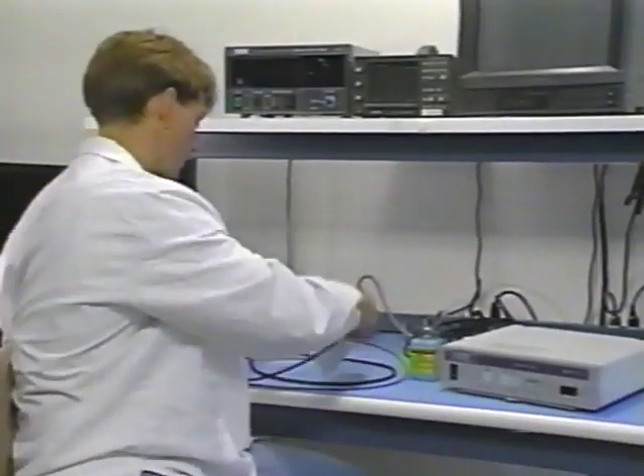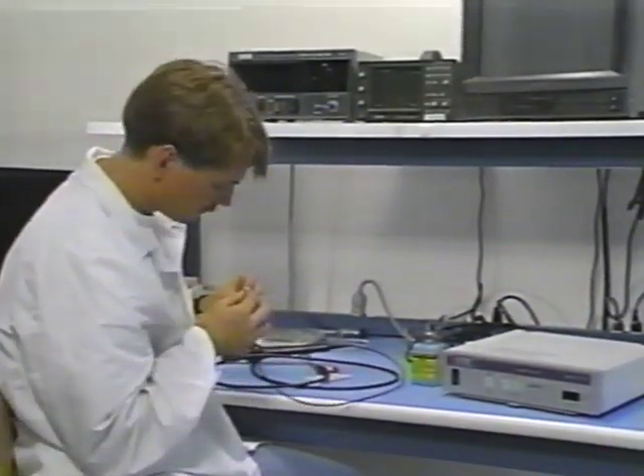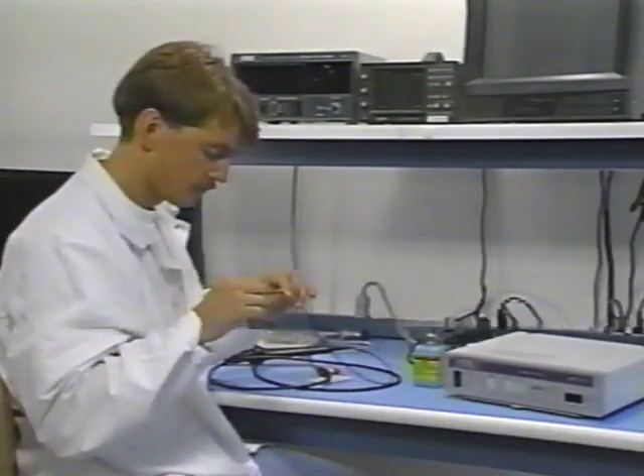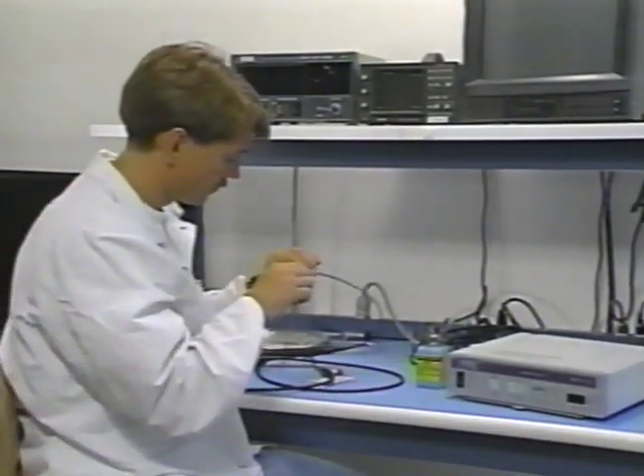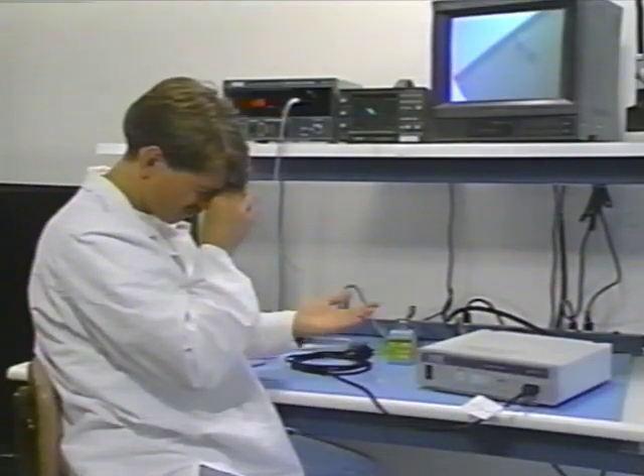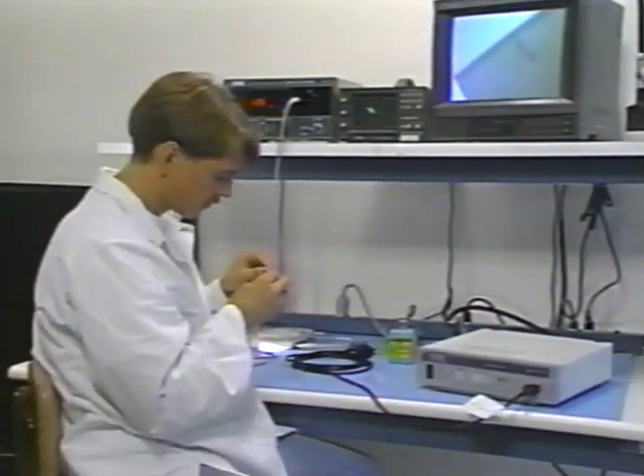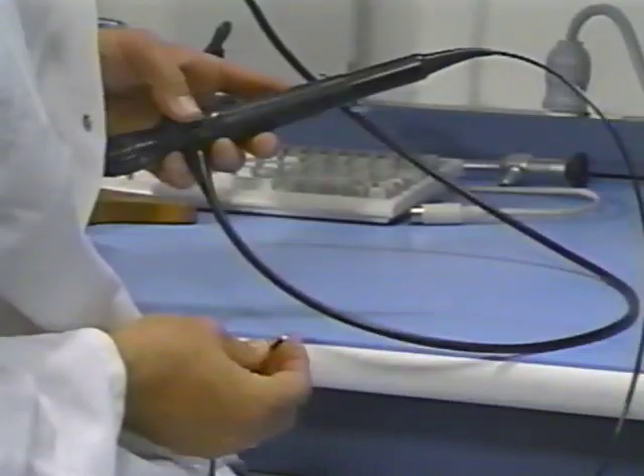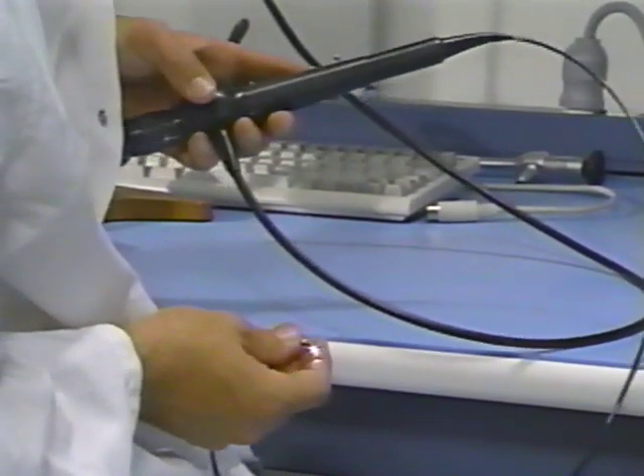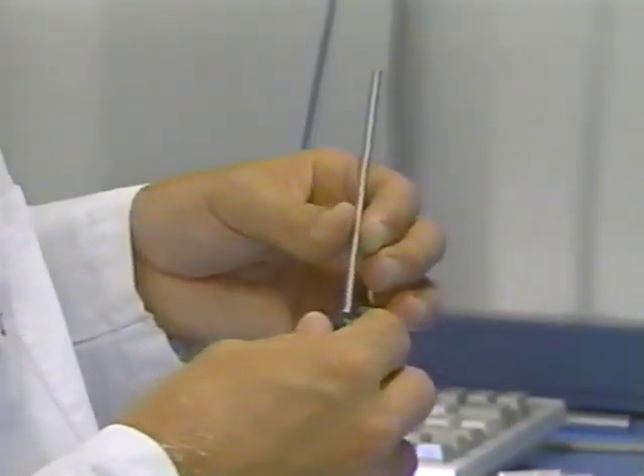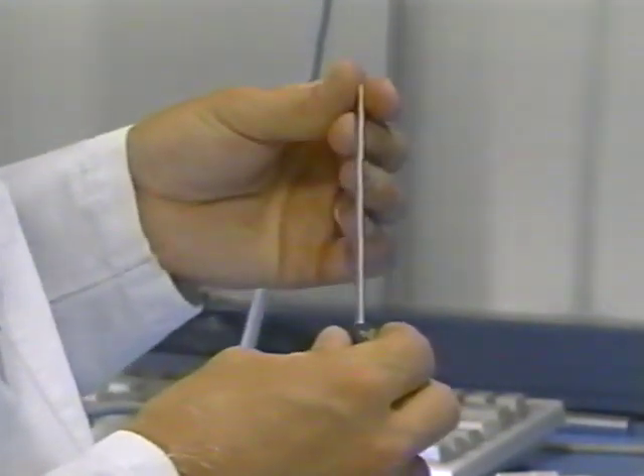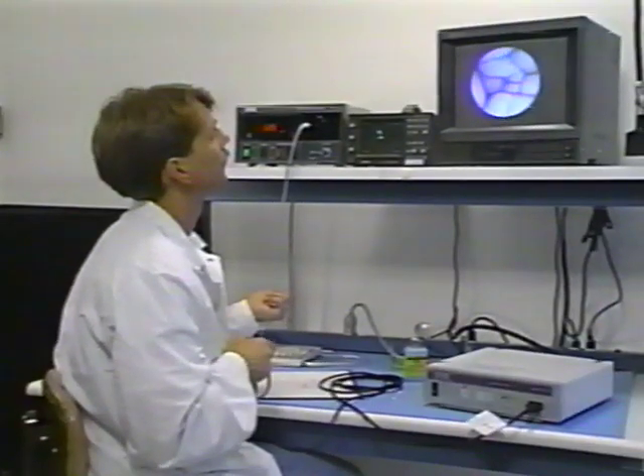Endoscopes can either be rigid or flexible. Like fiber optic light guides, they are easily damaged if banged, kinked, or dropped on a hard surface. You can check the endoscope post of a rigid scope for broken fibers in the same way you check the light guide cable. For flexible scopes, check the distal end for broken fibers. Run your fingers along the scope to check for kinks or bends. The image through the scope should be centered. If the image is off-center, there may be an optical problem within the scope. The image should also be clear and in focus.